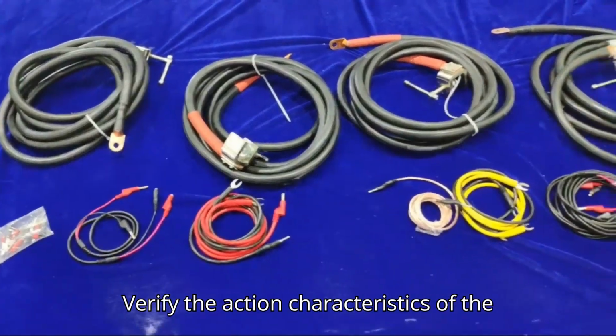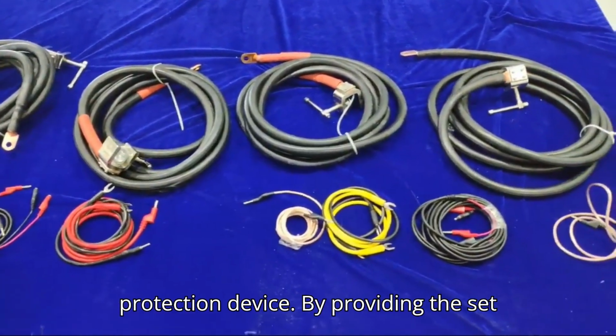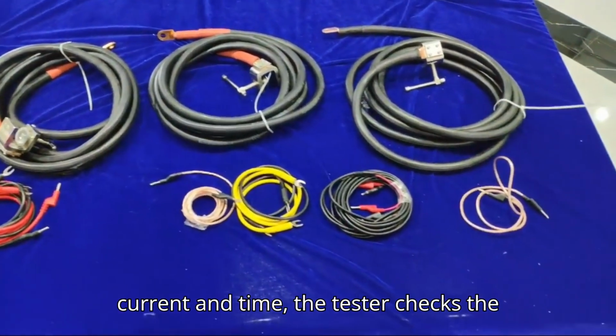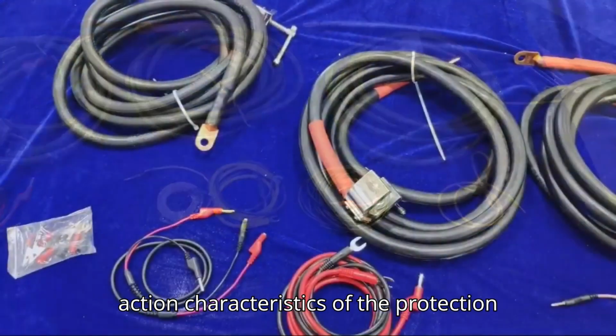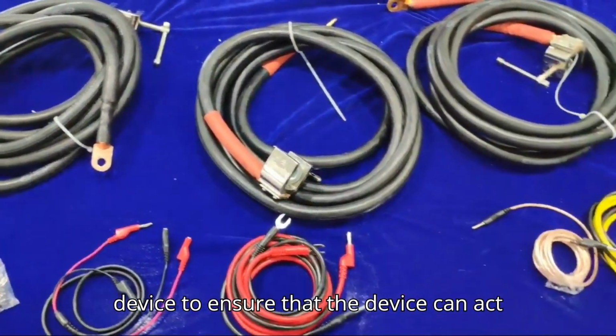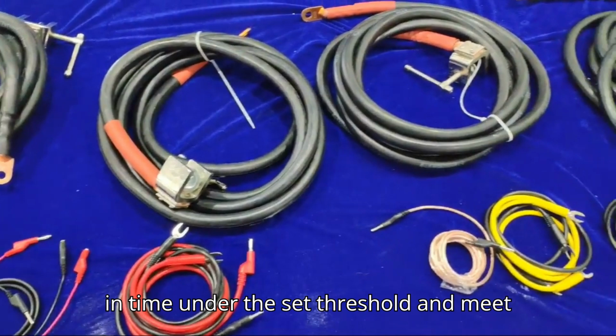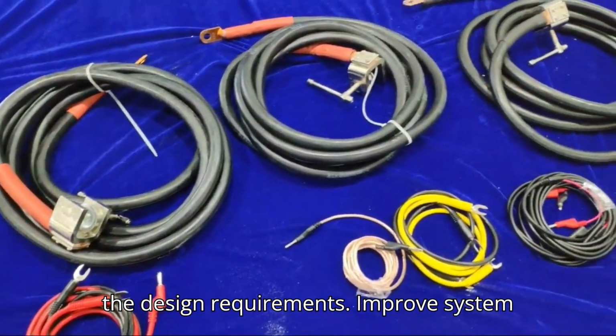Verify the action characteristics of the protection device. By providing the set current and time, the tester checks the action characteristics of the protection device to ensure that the device can act in time under the set threshold and meet the design requirements.